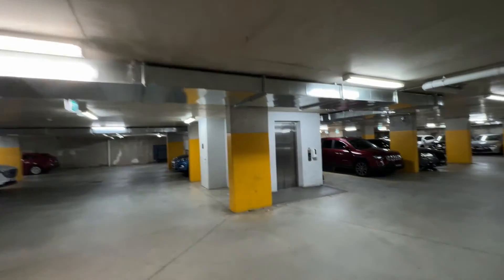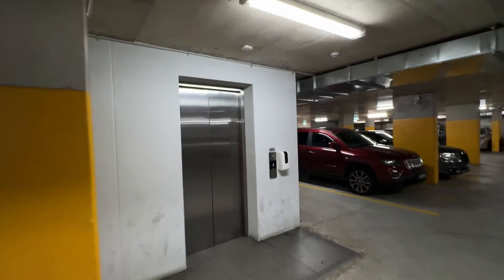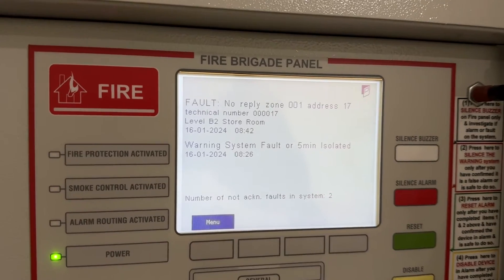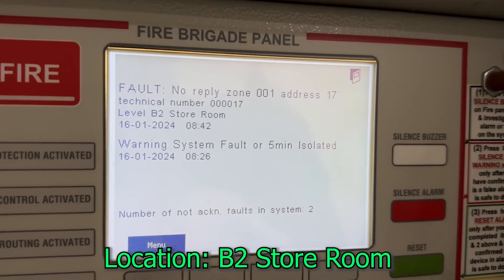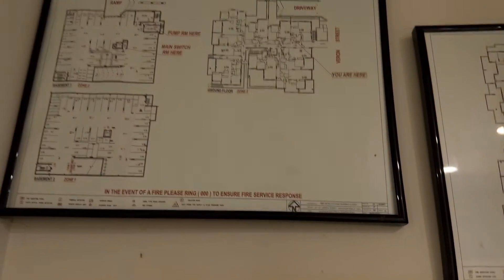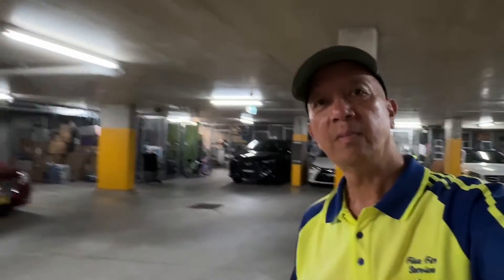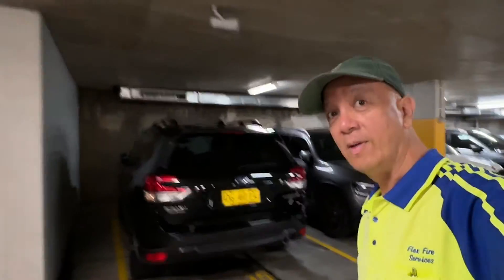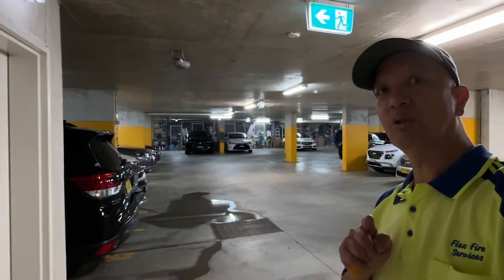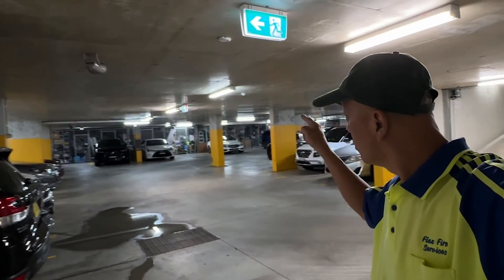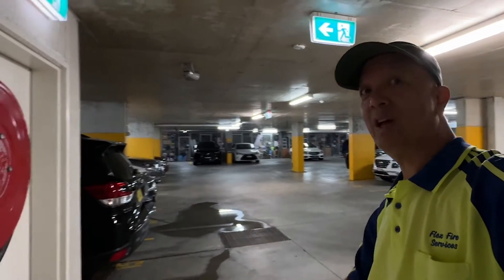Our next thing to do is look for the technical description of that particular detector. The detector 17 is listed as Basement 2, store room. Now you know 100% sure that the floor plan is wrong. According to the technical description, it will be located in Basement 2, store room. And on my way to that store room - that's the storage room. If the technical description is also wrong, you have to look for that red light one by one and check if any of these detectors have a steady red light.